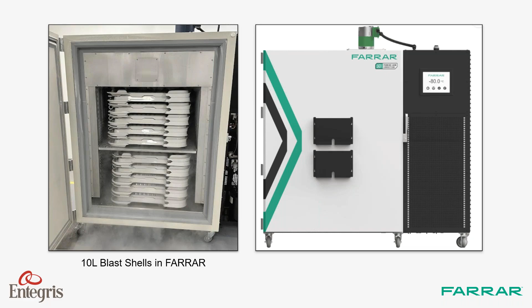The left picture shows the blast shells oriented in the chamber between our ductwork on the left and right. And the picture on the right is our control rate chamber LC model with the touchscreen HMI. This model has an easy profile programmer, ability to view the freeze process with a temperature graph, and also the ability to add a second probe for temperature tracking at the bag or bottle level. I'll explain the core system here on the following slides.